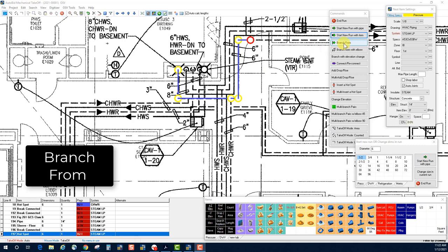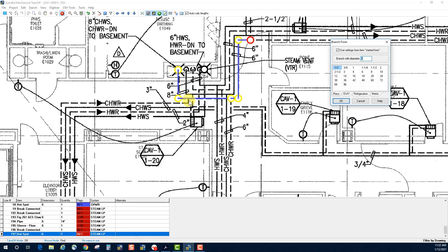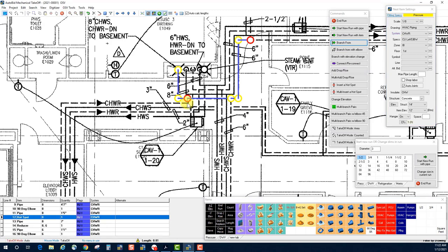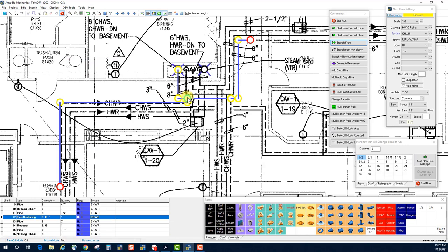The next command is Branch From, which is useful when you want to branch straight horizontally off a pipe. I've got a three-inch pipe coming off an eight-inch main, so when I hit the Branch From command, a window pops up asking me to verify the size — I'll put three — then I click where that branch starts and continue taking the pipe off. Clicking on the result, I can see it inserted a reducing T for me: an eight by eight by three reducing T.